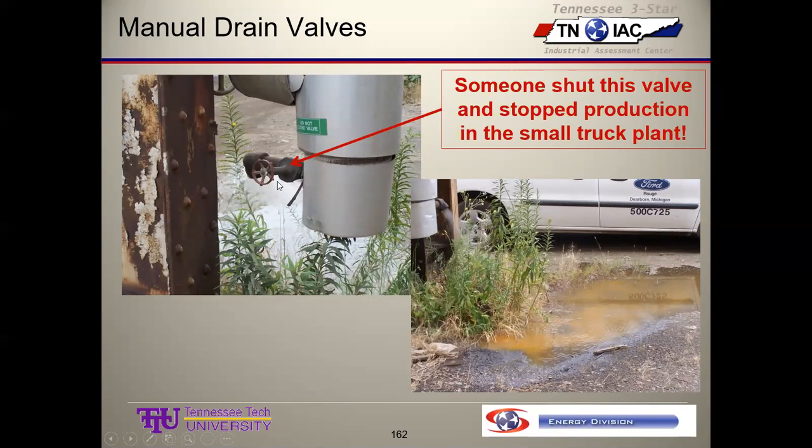This guy comes out there. He knew. He said, I know what's happened. He goes out there. He opens this valve. Look at the water rushing out of that thing. There was a puddle. I mean, that's probably half of the puddle. In some places, that puddle is like 6 inches deep. That was a big old pothole, and the water was still gushing out of that thing. We stood there for like 5 minutes, and what happens if you don't dry your air?